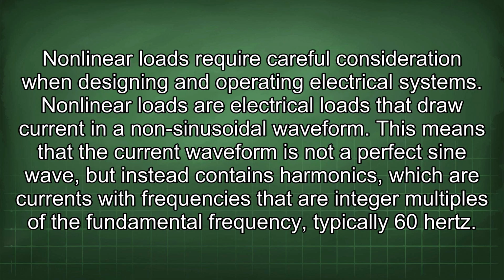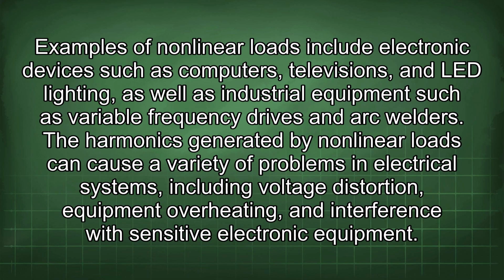Nonlinear loads require careful consideration when designing and operating electrical systems. Nonlinear loads are electrical loads that draw current in a non-sinusoidal waveform. This means that the current waveform is not a perfect sine wave, but instead contains harmonics, which are currents with frequencies that are integer multiples of the fundamental frequency, typically 60 Hz. Examples of nonlinear loads include electronic devices such as computers, televisions, and LED lighting, as well as industrial equipment such as variable frequency drives and arc welders. The harmonics generated by nonlinear loads can cause a variety of problems in electrical systems, including voltage distortion, equipment overheating, and interference with sensitive electronic equipment.